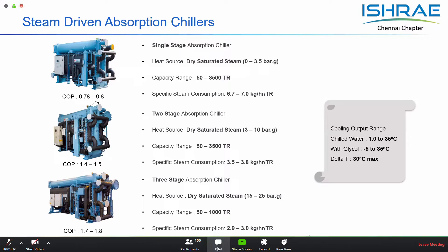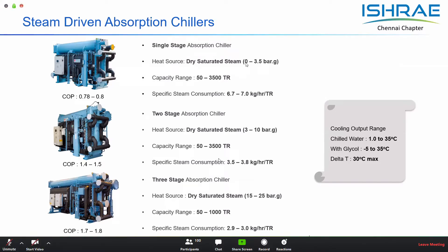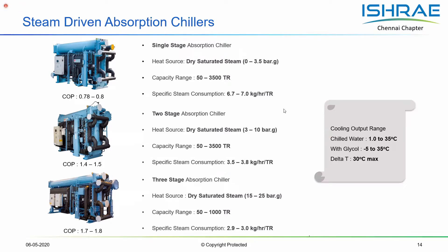Regarding the different types of absorption units, we have absorption units running on steam, which can be of different pressures. A single-stage unit can use steam starting just above atmospheric pressure up to approximately 3 to 3.5 bar as the driving heat source, with capacity ranges from 50 to 3500 tons. The specific steam consumption to produce one unit of refrigeration, or one USRT, is approximately 6.7 to 7 kilograms of steam per hour.